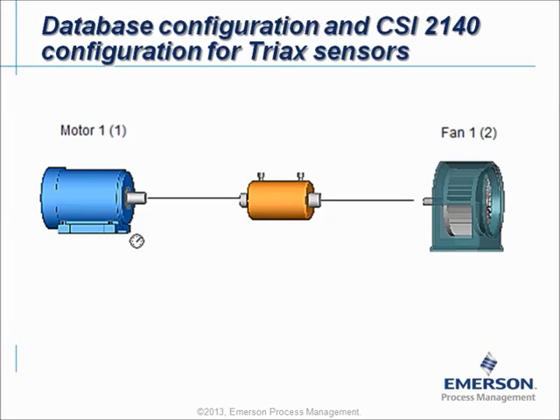Let's take a closer look at a live example. If we want to measure this machine using a Triax sensor and we install the Triax sensor always in horizontal direction, we have to install it on 4 locations: motor outboard, motor inboard, fan inboard, and fan outboard. So we will install the Triax sensor 4 times, always in horizontal and radial direction. What should we do in the database to make sure it is measured this way?